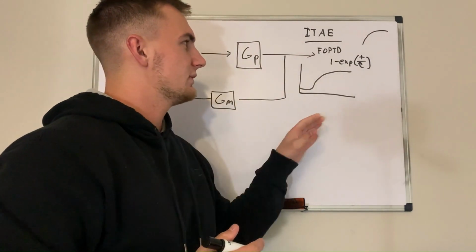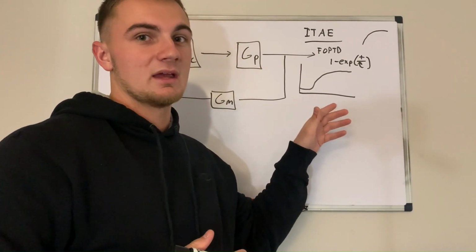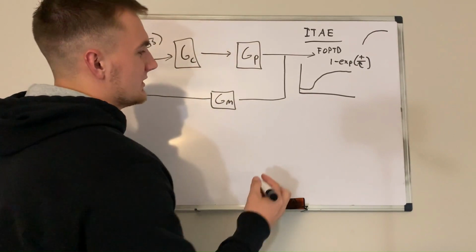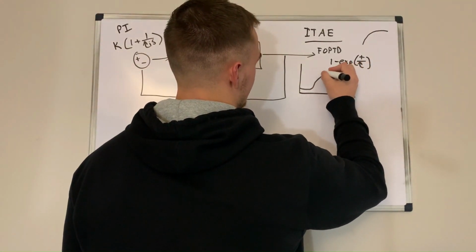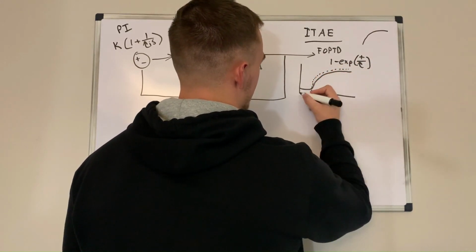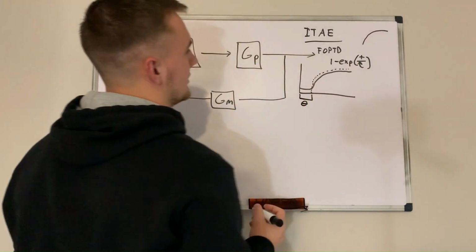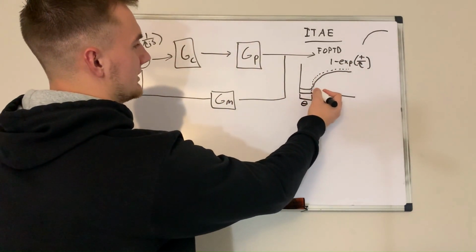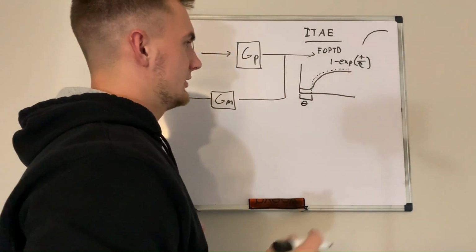But what we can do is approximate our data as a first order plus time delay system. And we can do this by essentially having the same plot here, except however, it comes straight down. So we have some dead time here, basically when our data does nothing from here to here, and then it starts looking like a first order function here.